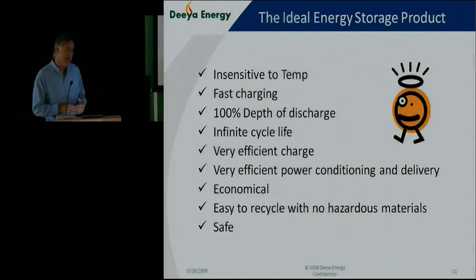They also need the capacity to be fast charged. The ideal situation is that you can charge the battery as quickly as you discharge it, but lead-acid batteries don't have that capacity. As they're charged over and over across time, it takes much more energy to get the battery back to a usable state of storage, up to approximately a 5-to-1 charge-to-discharge ratio.